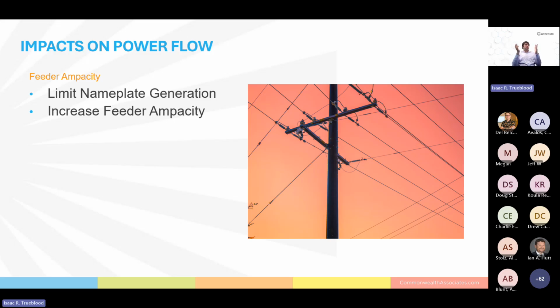But there's another wrinkle in this dilemma: multiple distributed energy resources can interconnect on the same feeder. Each distributed energy resource may individually not cause power flow concerns, but together they can surpass the system's rating and or cause backflow conditions. Who pays for these upgrades and how they pay is always a bit of a tricky situation. There are multiple schemes that can be used, but ultimately it must be considered and thought out in advance for both the distribution owner who's going to require those payments and the distributed energy resource owner, because they will have to be the ones paying the bill for most of them, usually.